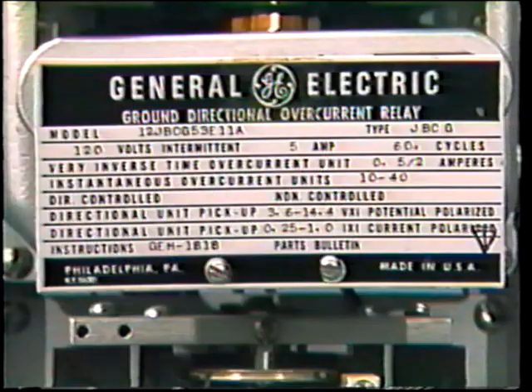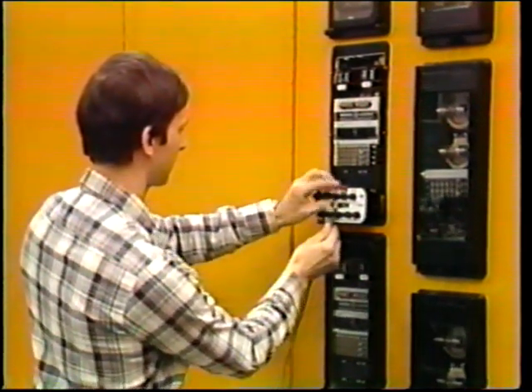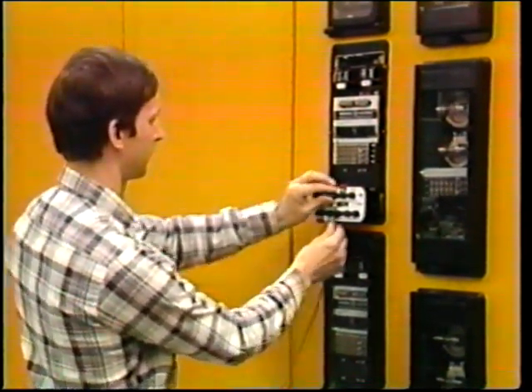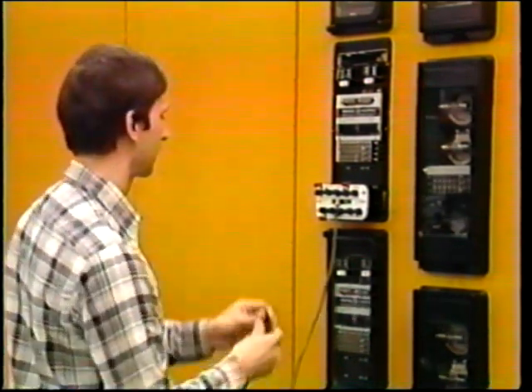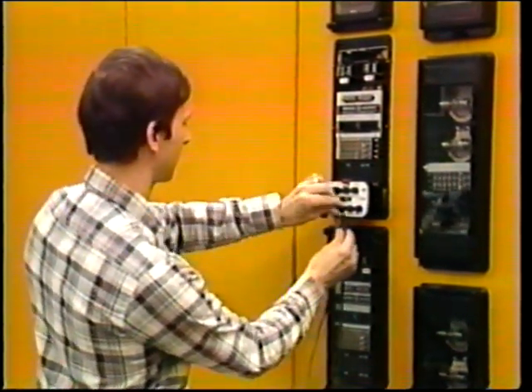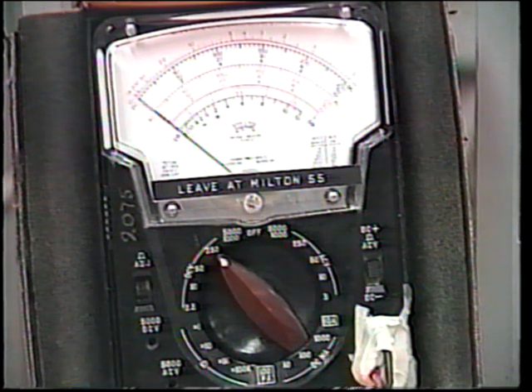However, further in-service load tests are required as soon as the equipment is placed online. This is because power flow is necessary to enable us to check the proper phasing of directional relays. Also, differential protection schemes are checked at light load to make sure that voltage and current measurements are balanced and correct for the intended relay functions. If you use a multimeter to check voltage sources at relays, make sure that it is not set on the amps range, otherwise it will short the voltage and trip the relay.